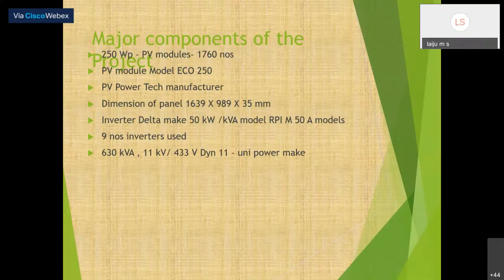So we are using PV Power Tech company's PV module, which has a capacity of 250, and such 1760 panels are selected because we required a capacity of 400, but we select 1760 panels, which is 10% more than the required capacity. So around 440 kilowatt of panels we have selected.